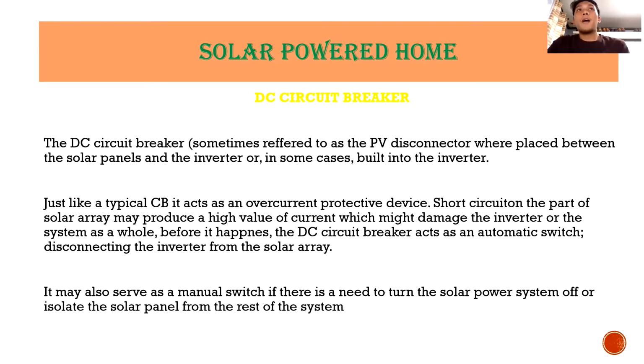If the system uses a battery bank, it must also be protected by a DC circuit breaker. The inverter, which converts direct current to alternating current, requires a DC circuit breaker at the source. Finally, if the user has an exclusive electric panel for DC loads, an array of DC circuit breakers will be required.